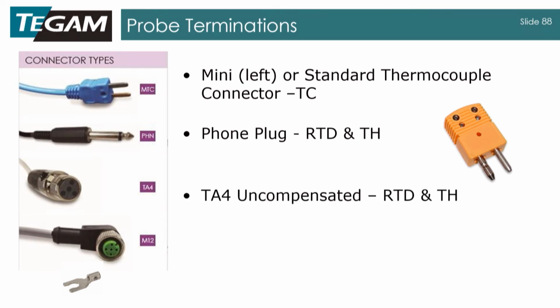Next is called the TA4 uncompensated. What uncompensated means is that all of the connectors are copper. So you wouldn't want to use this with something like a thermocouple because you're introducing new dissimilar metals and new thermocouple junctions. So this is going to be best for RTD and thermistor applications.